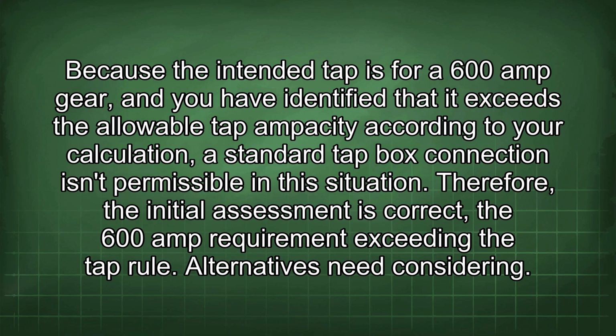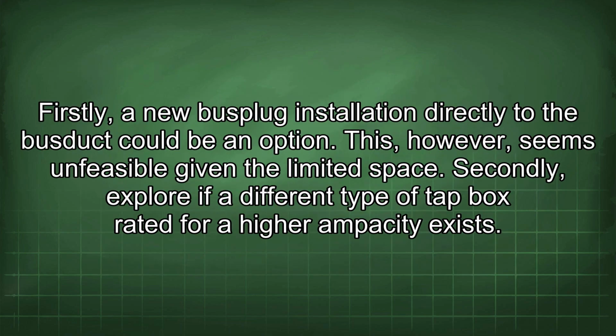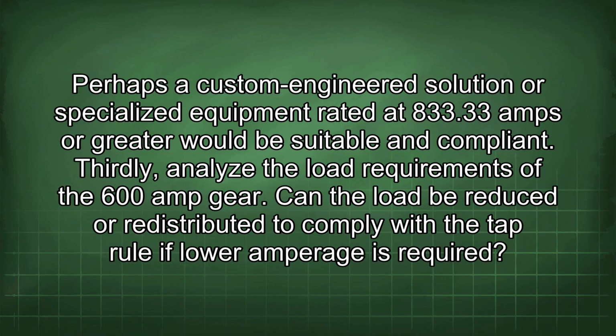Alternatives need considering. Firstly, a new busplug installation directly to the busduct could be an option. This, however, seems unfeasible given the limited space. Secondly, explore if a different type of tap box rated for a higher ampacity exists. Perhaps a custom-engineered solution or specialized equipment rated at 833.33 amps or greater would be suitable and compliant.